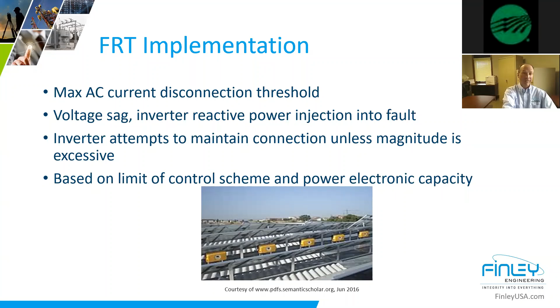And the newer ones are going to do a little bit better job with the ride-through capability. And this is the bottom line, this is why I bring it up, and why the thrust is here in the first place. Our systems, the way we built them, even with smart distribution breakers, the traditional hydraulic device wasn't designed to handle a high-level impact of these things coming on. Maybe if you've got one or two on a feeder you don't see the impact and you're fine, but you either get scale issues with multiple systems or single larger systems. The question is, have you analyzed your distribution and protection schemes to know they can mitigate the things we've been talking about?